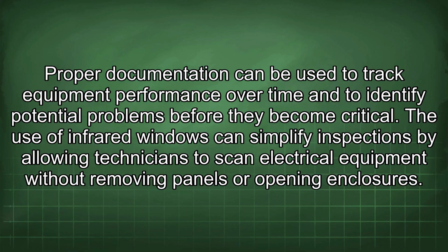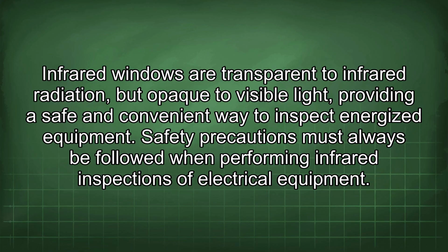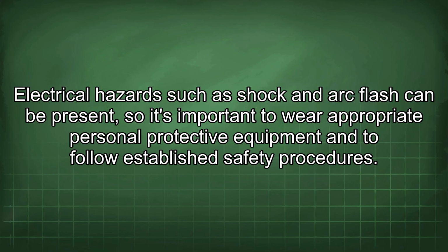The use of infrared windows can simplify inspections by allowing technicians to scan electrical equipment without removing panels or opening enclosures. Infrared windows are transparent to infrared radiation but opaque to visible light, providing a safe and convenient way to inspect energized equipment. Safety precautions must always be followed when performing infrared inspections of electrical equipment. Electrical hazards such as shock and arc flash can be present, so it's important to wear appropriate personal protective equipment and to follow established safety procedures.